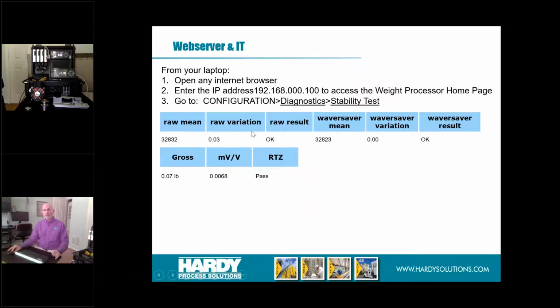So with no vibration, you would get an okay on the raw result. Once you put vibration, you would get a fail on this. And then if you added the WAVERSAVER, you hopefully get an okay. Now, if you remember when I put the 7.5 hertz filter, we still had a little jumping around. Very likely you would have gotten a fail on this one. Once we went to the 3.5 filter, now this one would have given you an okay.